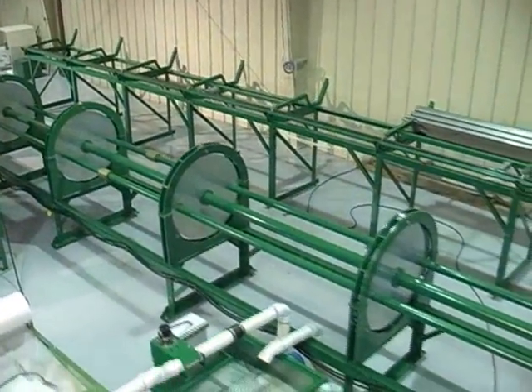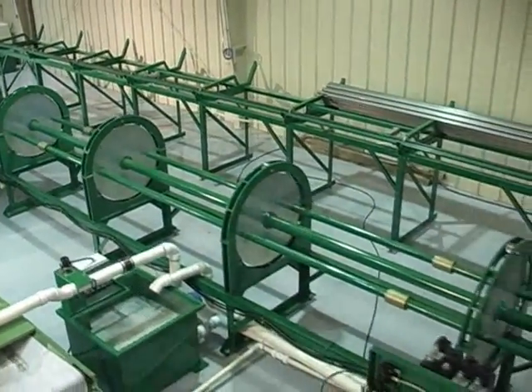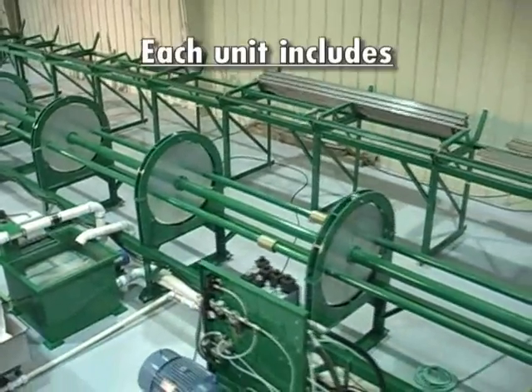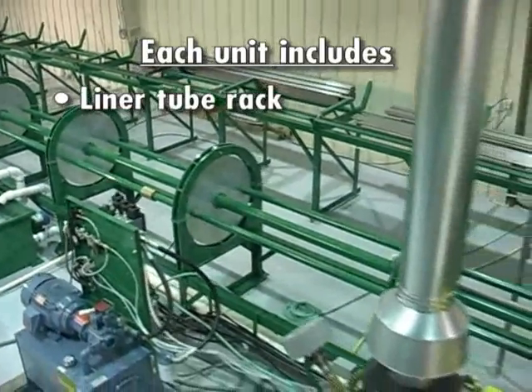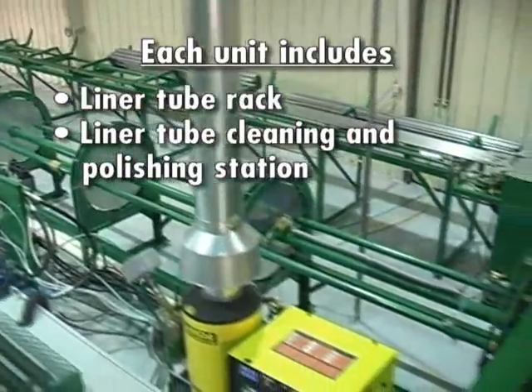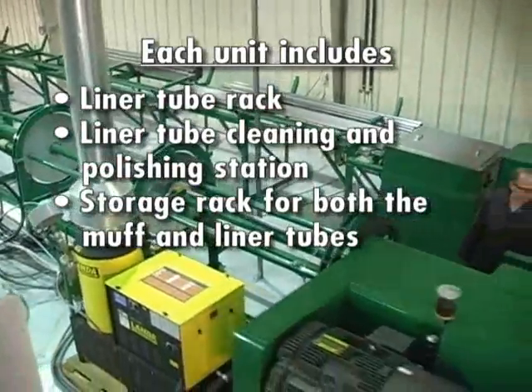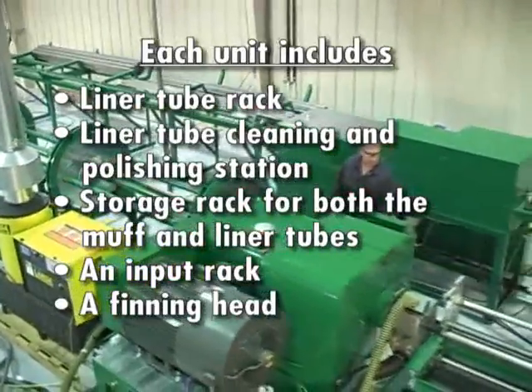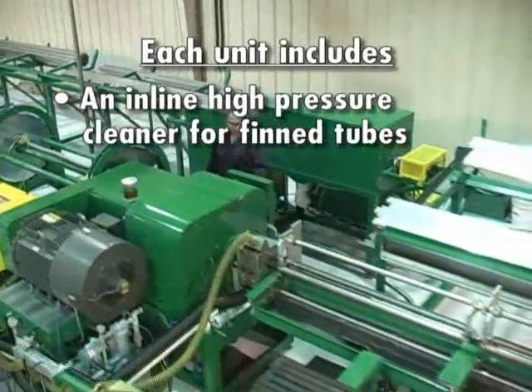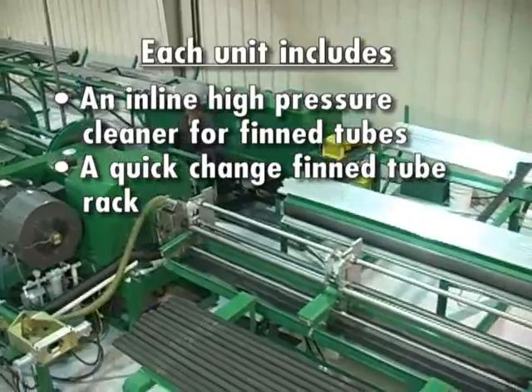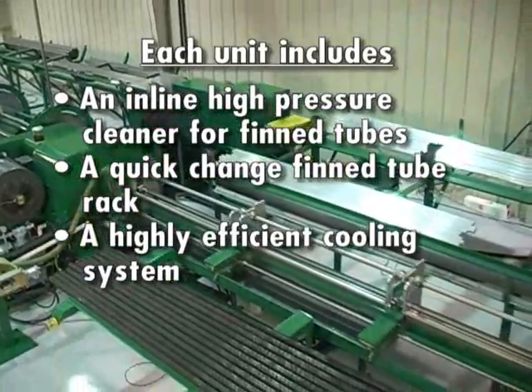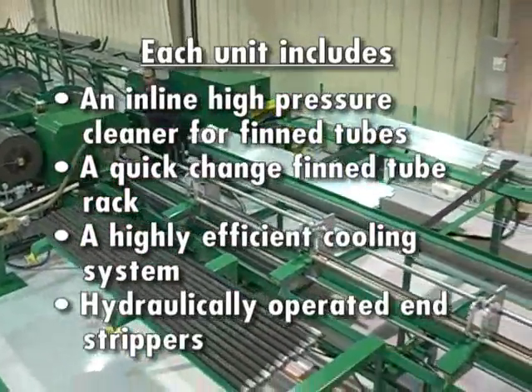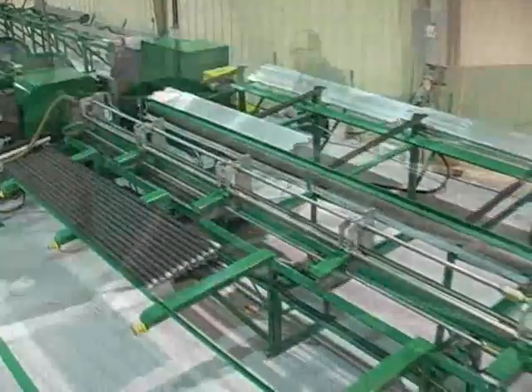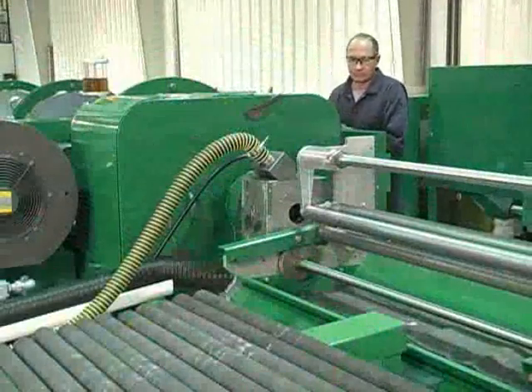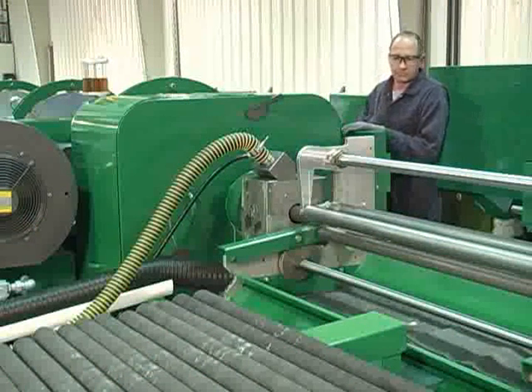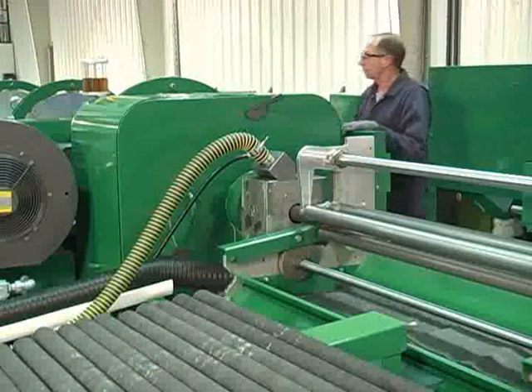An extruded fin tube machine is a complete system for the handling and manufacture of extruded fin tubing. Each unit includes liner tube rack, liner tube cleaning and polishing station, storage rack for both the muff and liner tubes, an input rack, a finning head, an inline high-pressure cleaner for fin tubes, a quick-change fin tube rack, a highly efficient cooling system, and hydraulically operated end strippers. The machine is designed to be set up so while one tube is being finned, another is being loaded in preparation for the next finning operation.